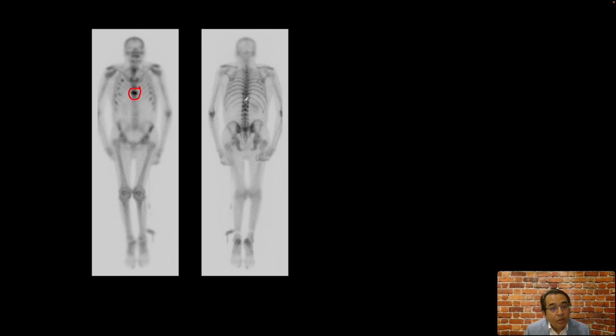The anatomy that is closer to the camera head is better visualized on images, and the anatomy that is further away from the camera head is not well visualized. So on this posterior image, the spine is closer to the camera head, so that is better visualized.